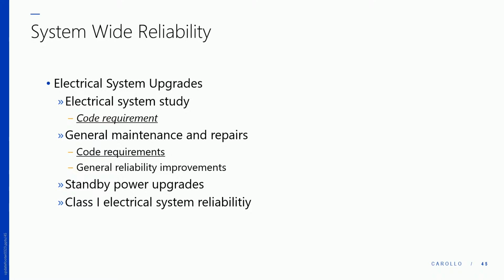Yes, sir. Okay, but I wasn't following what you were saying. I was thinking that you were putting all this power in. No, we're not increasing electrical demand. We're just essentially creating redundancies in the electrical systems so that it's more reliable. And we're promoting resiliency. If there were ever an arc flash or a fault at any point in the system, you have at least half of the plant that you can continue operating, because you have two trains, half of the plant on one train and the other half of the plant on the other train.